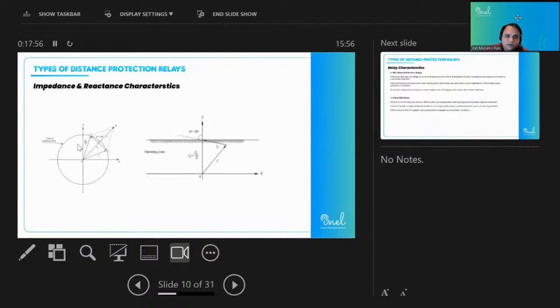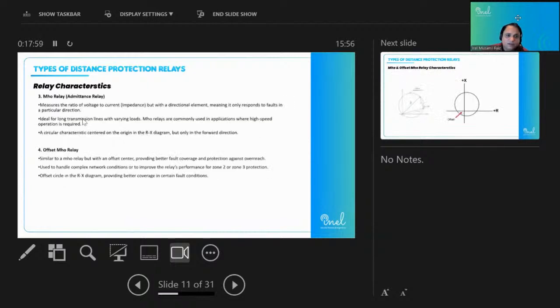But this drawback is settled in this MHO relay or admittance relay. So it has an inherent directional characteristic, which is used in detection of a fault in only one direction. If the fault is on the back side of the line, then it will not detect it, but it will wait for the other relay to operate. And this characteristic is ideal for those lines which are longer in length and heavily loaded.